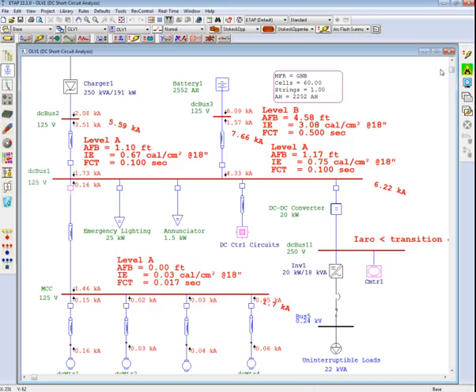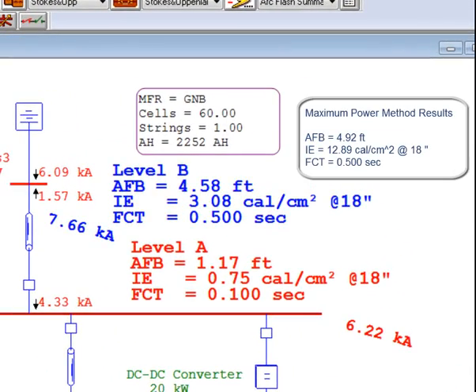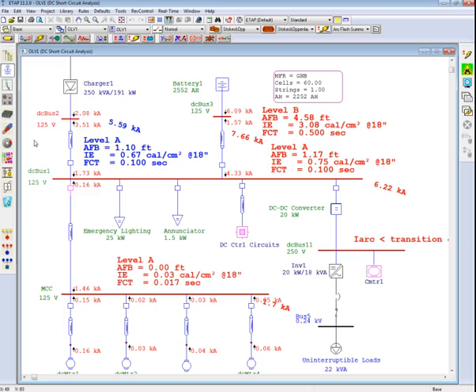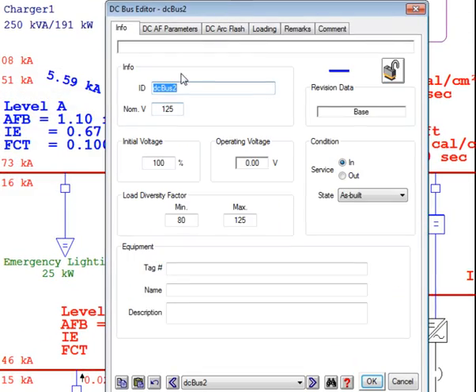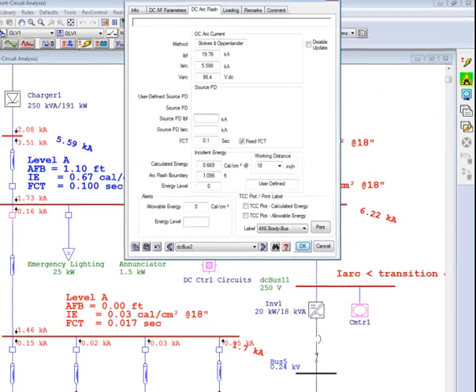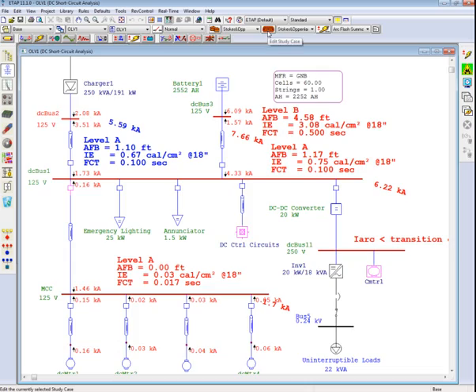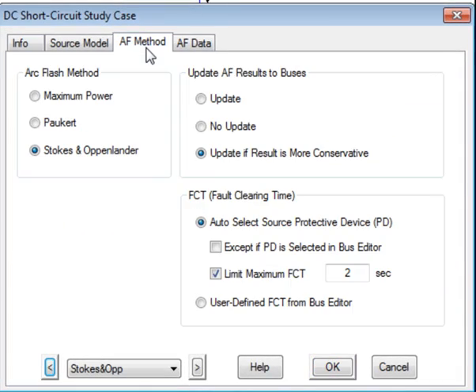This method attempts to calculate the actual magnitude of the arc fault. The results of this method should be more realistic when compared to that of the maximum power method. If we double click on DC Bus 2 and look at the DC arc flash page, we will see that the values on the one-line have also been updated in the editor. ETAP will always update the values in the bus if the results are more conservative. This is an option in the study case listed on the arc flash method page, where the user can configure the study case editor to update the bus results with the highest values into each fault location.